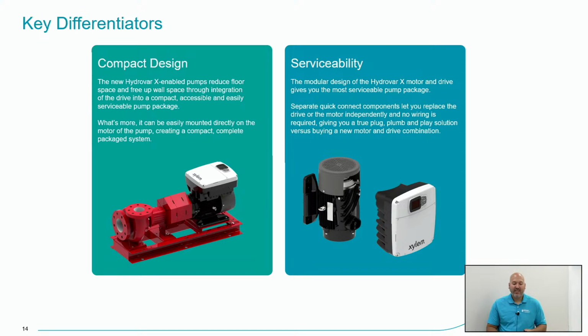Next is a compact design. The example I like to give: if you're looking at a traditional 15 horsepower induction motor, and you were to take that and look at our 15 horsepower Hydrovar X solution, the circumference of the motor and VFD together of the Hydrovar X is the same circumference as a 15 horsepower induction motor by itself. So the motor here is significantly smaller compared to a traditional induction motor, and with the VFD on there, you are still getting a more compact footprint.